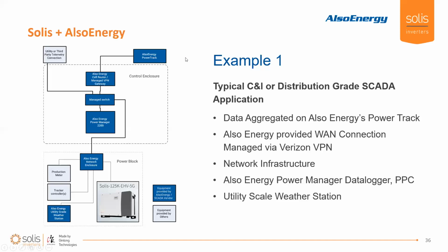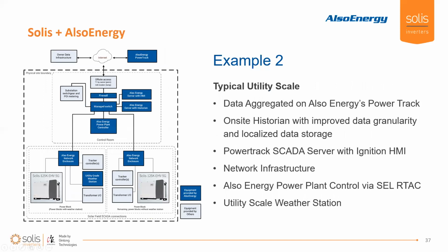In this next slide, we have a second example of a typical utility scale system. You see here the architecture of a typical utility scale application—this may be a large scale DG all the way up through a 100 megawatt AC plant. You'll see a lot of similar parts and pieces: the network infrastructure, the utility grade weather station, the interface to the Solis inverters. That architecture is very similar. Some added features: typically we're dealing with a hardline connection, so we add a firewall for network security local to the site. We also add two servers, one for dedicated HMI leveraging the Ignition HMI application to provide the PowerTrack SCADA server, and an on-site historian where we build a local SQL historian for all that data to be displayed within the HMI.